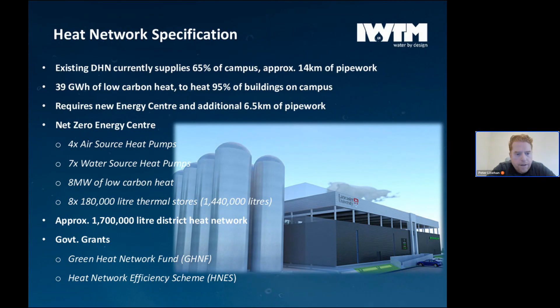So whenever you have a heat network, no matter how large it is or how small, you're going to have 2 choices. You're going to choose whether to go down the traditional chemical dosing route or the innovative chemical-free route. With this size system, you're going to have a huge environmental footprint that you have to consider. Just to initially fill the system to prevent corrosion, if you're going to use chemicals, you're going to use approximately 10 tons of chemicals.